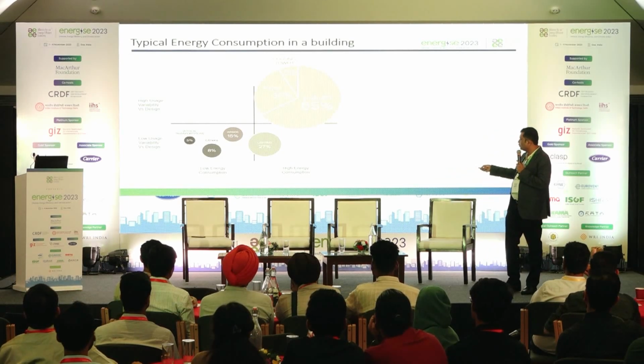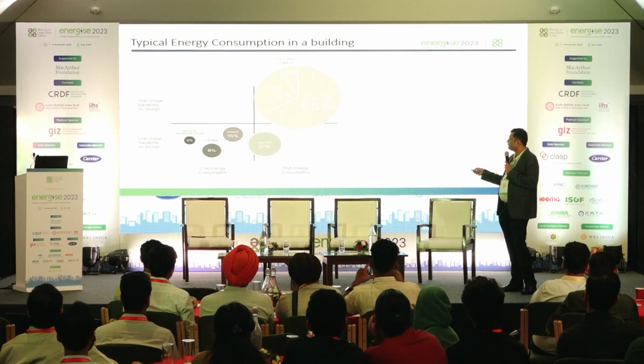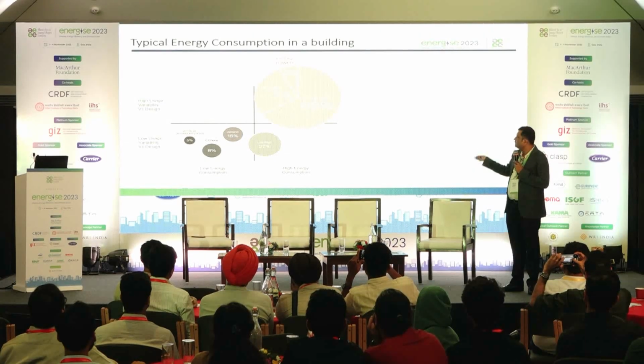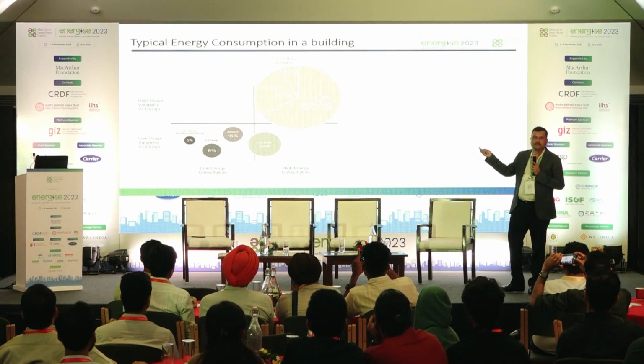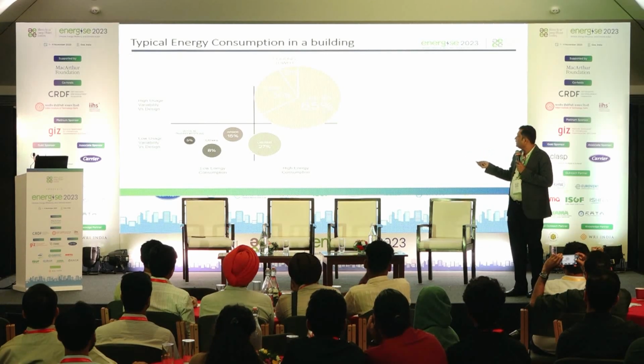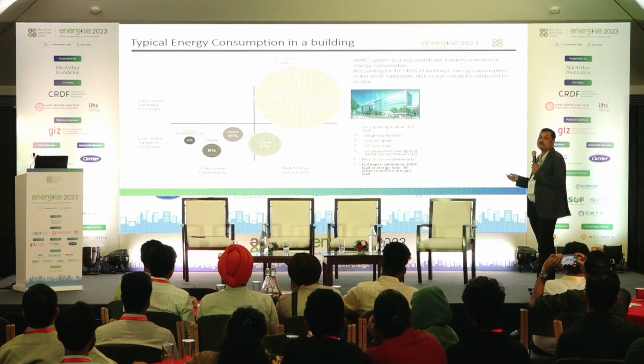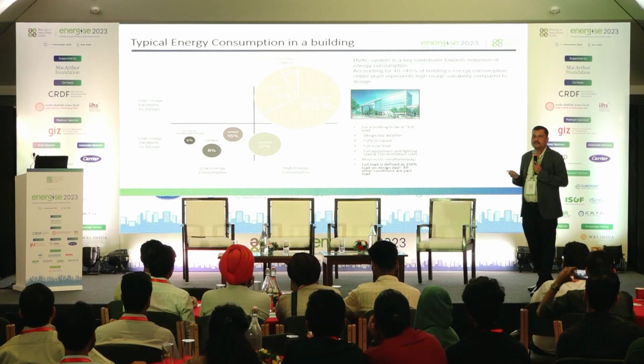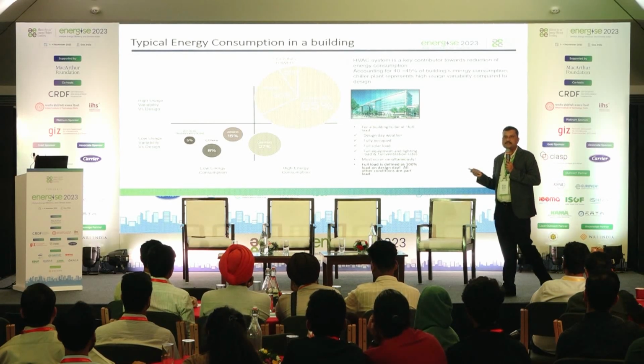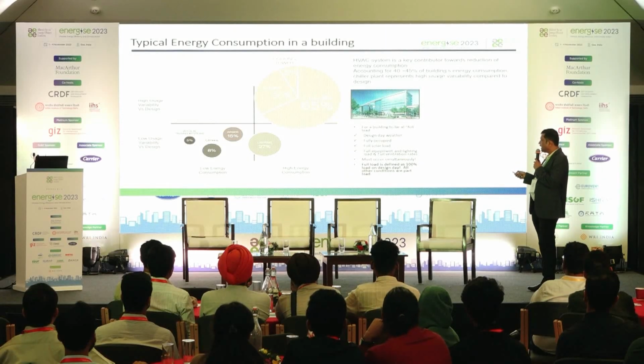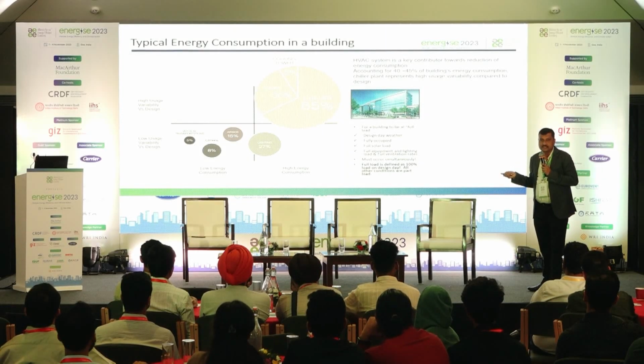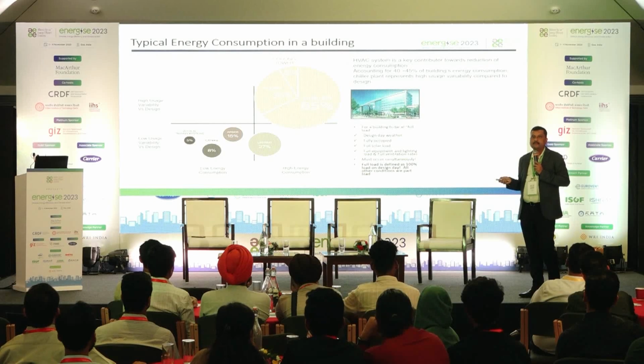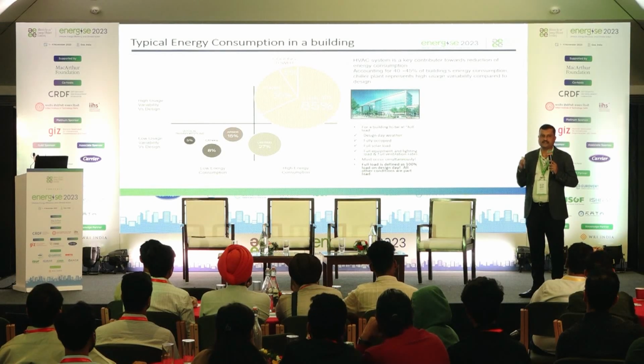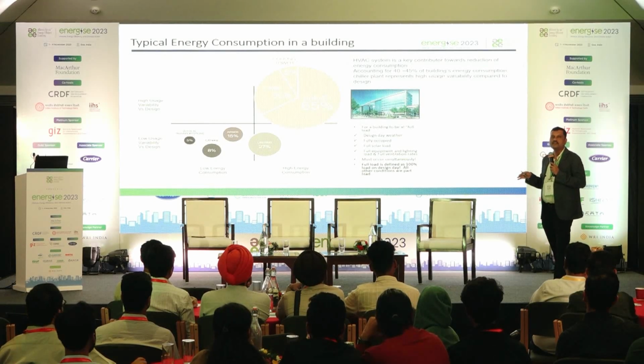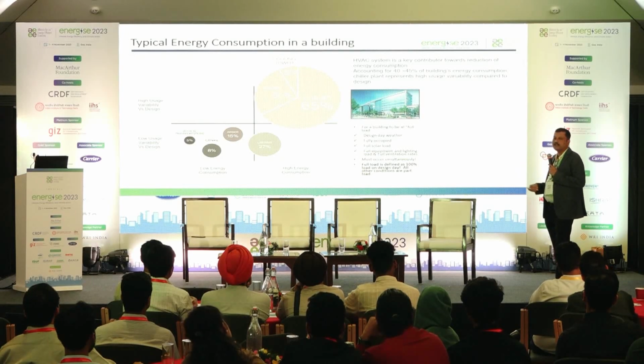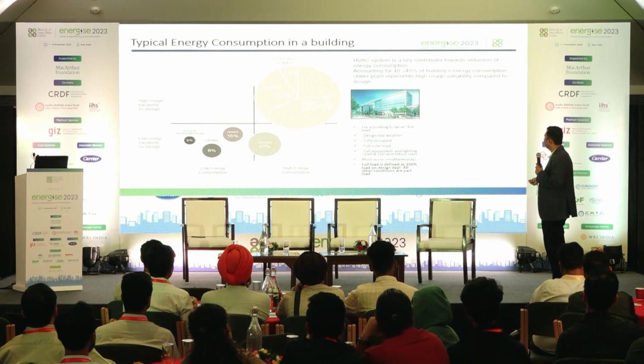But moving towards the right-hand side, you have lighting, and then the major chunk comes from HVAC. What makes it close to about 40 to 45%? Based on zone, climate, and multiple things, it's about 40 to 45%. Out of that, chiller is about 65% of energy consumption in any plant. That's why people put a lot of effort and emphasis on buying an efficient chiller, followed by pumps, cooling towers, and other energies.